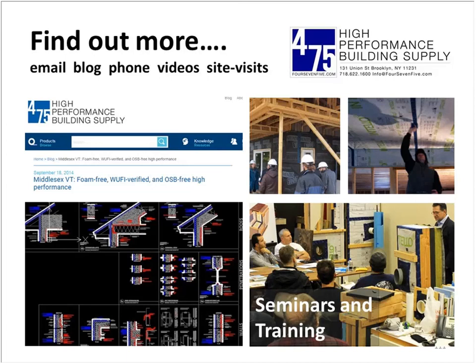The idea would be to have a really tight, high performance enclosure. There's a question about whether passive house or airtight enclosures belong in hot and humid climates. But the fact is, they do belong is the short answer. These buildings' energy uses are driven by dehumidification because they've got leaks and they've got all this hot and humid air moving through the building that they're trying to dehumidify. So by keeping that hot and humid air out, you're driving down those energy load requirements and maintaining a much more controlled, better environment.